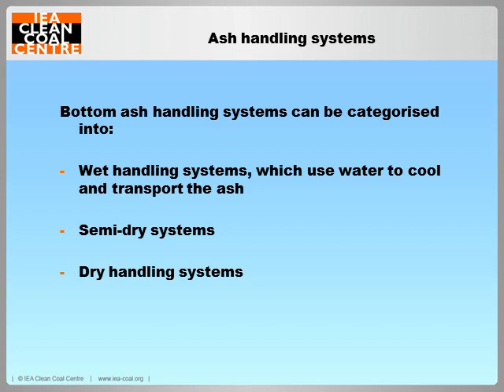Right, moving on to ash handling systems. Ash formed during the combustion of coal needs to be removed from the bottom of the boiler. Systems for handling this bottom ash, sometimes called clinker ash, can be categorised by their water usage into wet handling, semi-dry and dry handling systems. Today I'm just going to discuss the semi-dry and dry handling systems, which use less water than the wet ones. In wet systems, water is used to both cool and transport the ash.